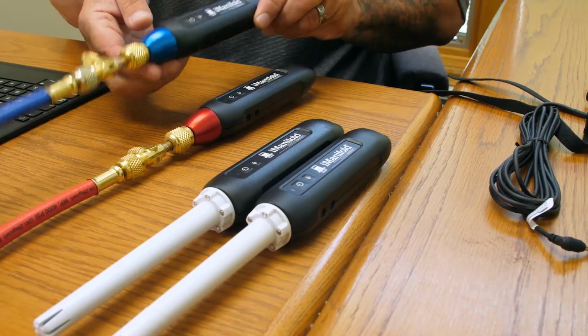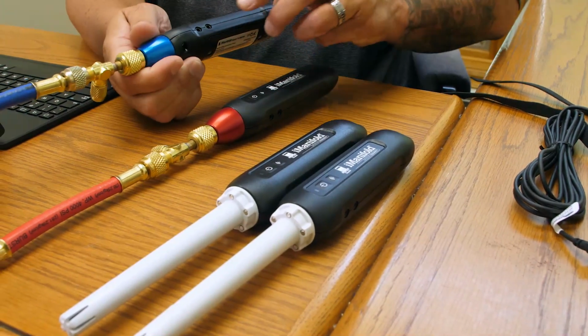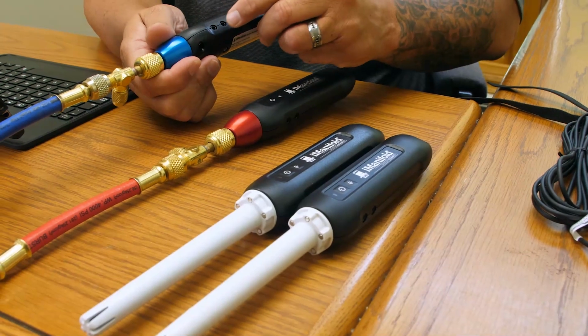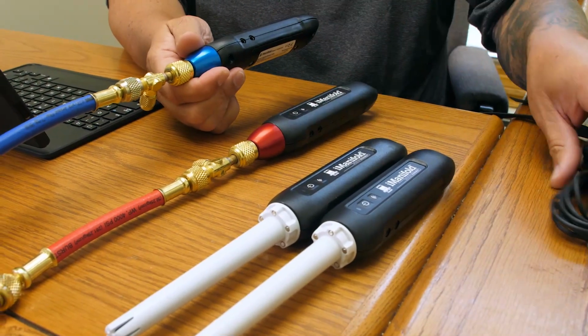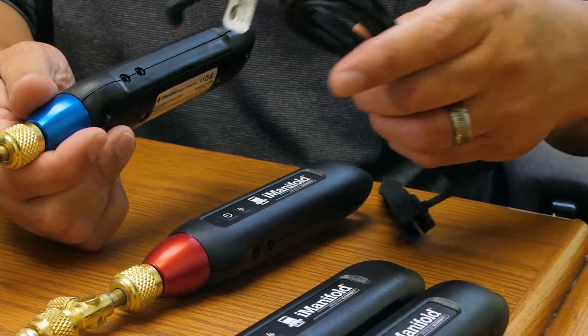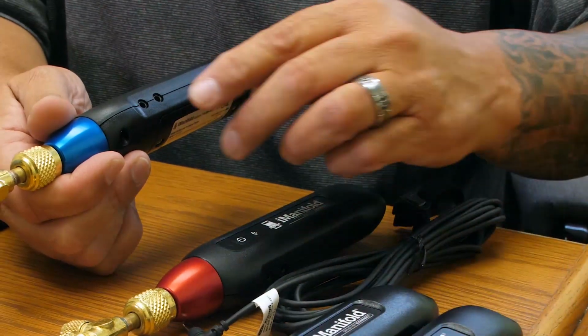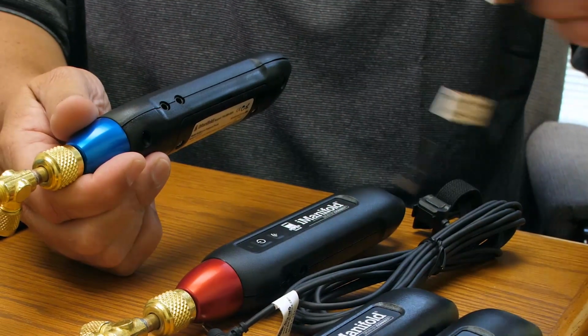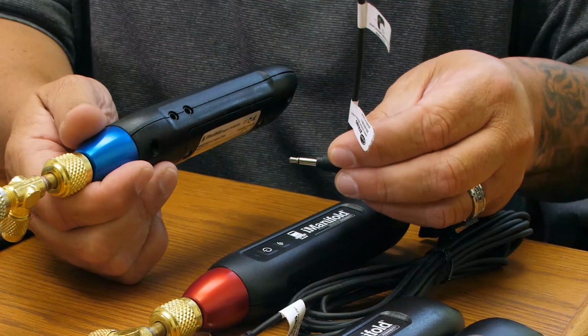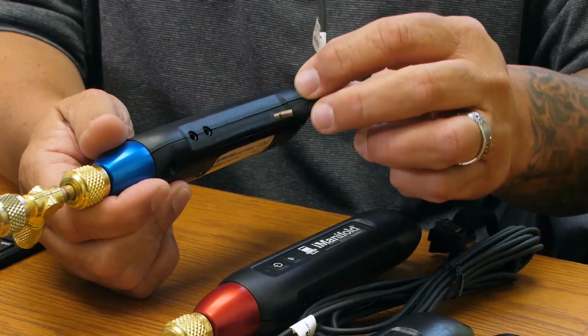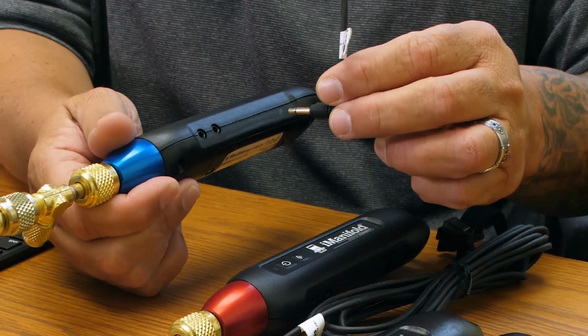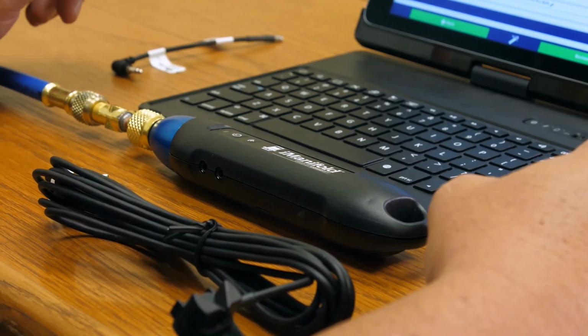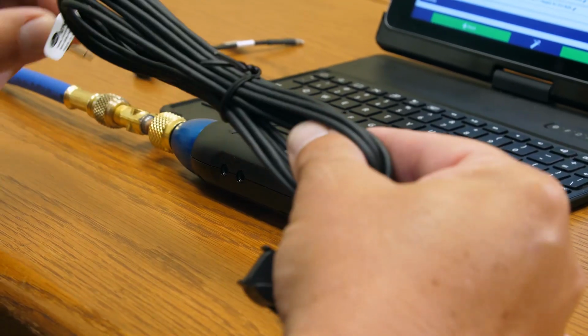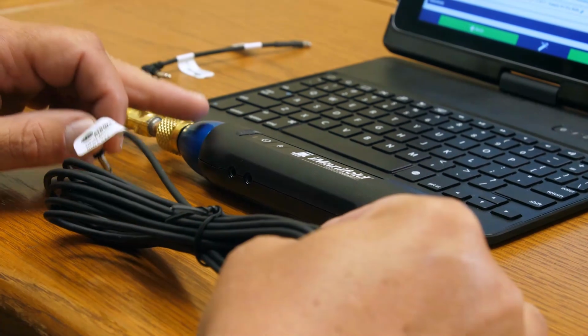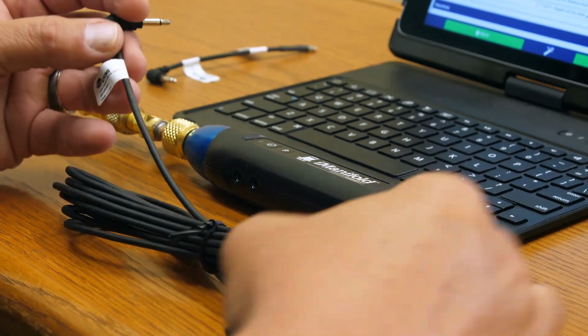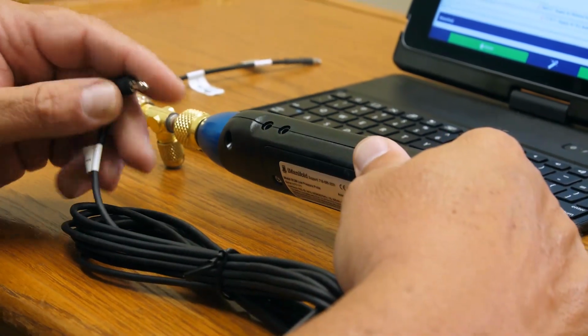We're going to start with our low side probe, the temperature inputs on the side, T1 and T2. We're going to be using our strap probe here in T1 for our suction line temperature. And we're going to be using our 4-inch ambient air temperature probe in T2 to get our ambient air temperature at the condenser. We're going to start by plugging in our thermistors. We're going to use our 901M strap type thermistor on our low side for our suction line temperature. We're going to plug that in to T1.